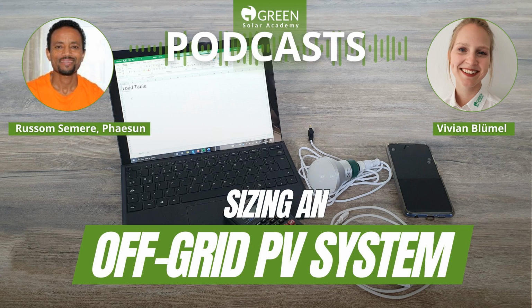So the solar module is important to know because this is the generator of the energy. And so whatever demand I have on the energy side, for example, if I have a 100 ampere hour requirement, my solar panel should be able to produce this amount of energy plus the losses in the cable and the losses in the different components. So the solar module is important, and you need to know the energy consumption of the house for this.